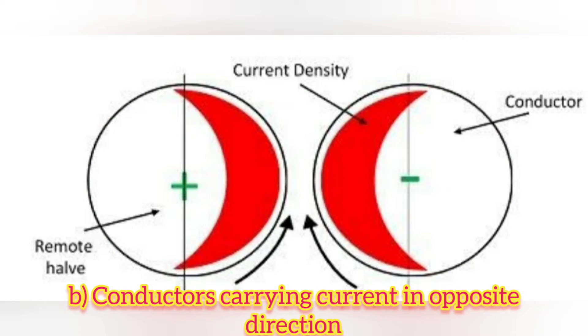In the second case, when conductors carry current in opposite directions, the close part of the conductor carries more current and the magnetic field of the far half of the conductors cancel each other. Thus the current is zero in the remote half of the conductor and crowded at the nearer part of the conductor.